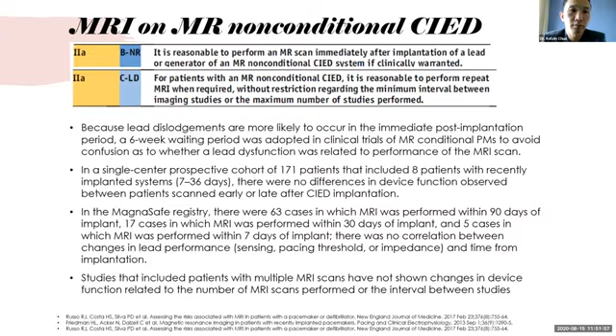So there are also guidelines for monitoring of devices if there are significant changes in parameters post-MRI. You need to know that these guidelines recommend that these parameters are like a pacing threshold change of more than 1 volt, the sensing P wave or R wave decreased by more than 50% from baseline, a pacing impedance change of more than 50 ohms, a shock impedance change of more than 5 ohms. Of course, I think there may sometimes be measurement changes, but these are the parameters that are given by the guidelines.